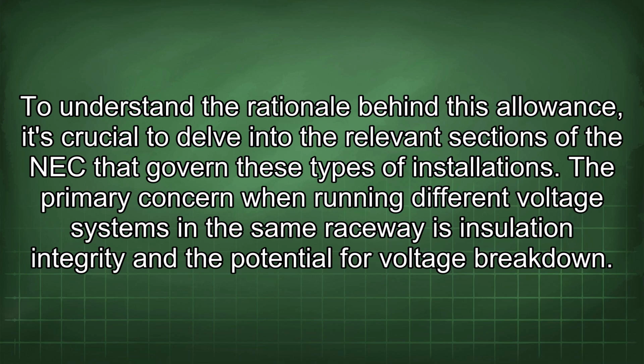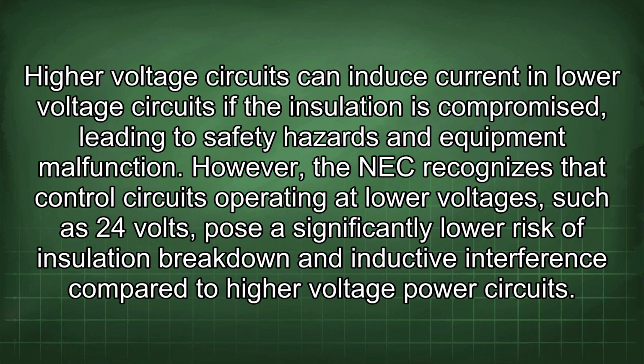To understand the rationale behind this allowance, it's crucial to delve into the relevant sections of the NEC that govern these types of installations. The primary concern when running different voltage systems in the same raceway is insulation integrity and the potential for voltage breakdown. Higher voltage circuits can induce current in lower voltage circuits if the insulation is compromised, leading to safety hazards and equipment malfunction. However, the NEC recognizes that control circuits operating at lower voltages, such as 24 volts, pose a significantly lower risk of insulation breakdown and inductive interference compared to high voltage power circuits.